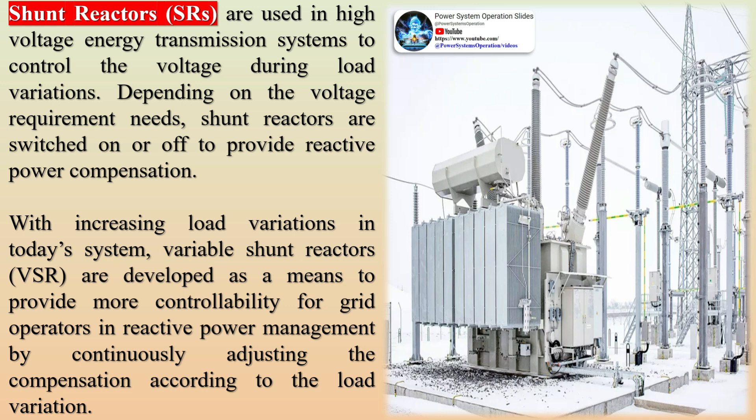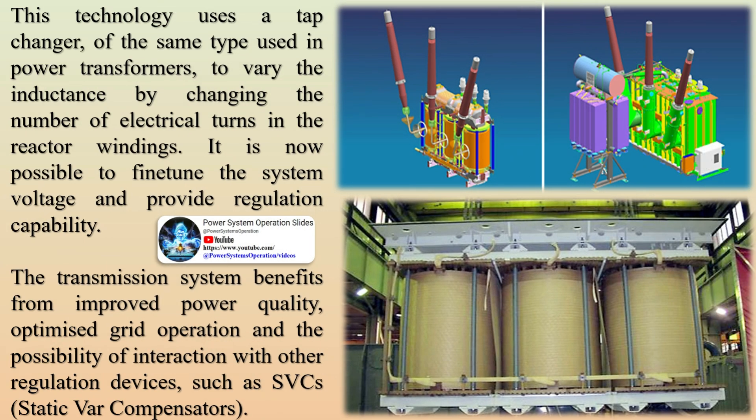This technology uses a tap changer, of the same type used in power transformers, to vary the inductance by changing the number of electrical turns in the reactor windings. It is now possible to fine-tune the system voltage and provide regulation capability.